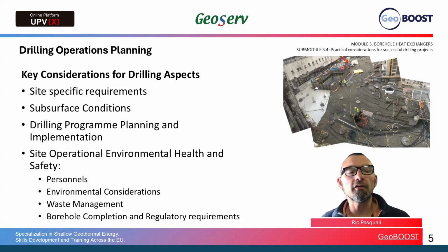The other two key aspects relate to waste management, and how the waste from the drilling operations is managed, and then obviously the borehole completion in line with the regulatory requirements. So if there are any regulations that are specific to completing borehole heat exchangers in terms of grouting and grouting materials selected, or indeed if these are water-to-water systems using open loop groundwater solutions, the actual completion of the borehole in terms of casing and grouting of that casing to achieve environmental protection needs to be considered at an early stage.